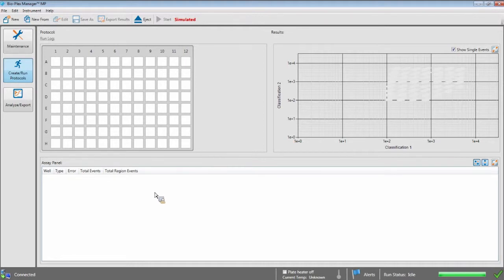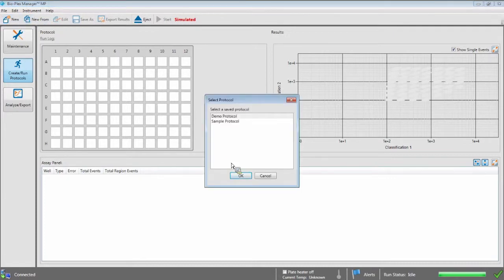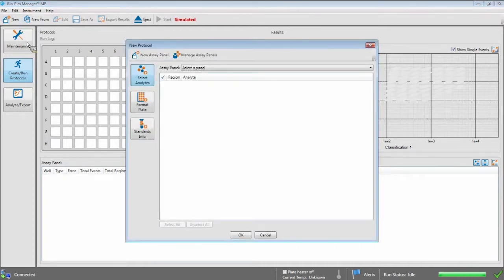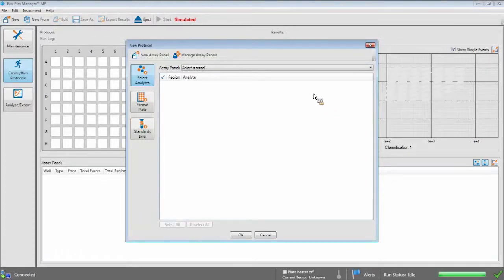The first step for a new run is to create a protocol. Go to the upper left corner and click on the New button. If you would like to run a previously saved protocol, click on the New From button and select the protocol to modify or rerun. When you click on the New button, you'll see a pop-up window which will walk you through the steps to create your protocol. The first step is to select your analytes so the MagPix knows what regions to display the data from. While the MagPix does record data appearing in any region, limiting the display to the actual targets in the assay will help prevent low bead errors.